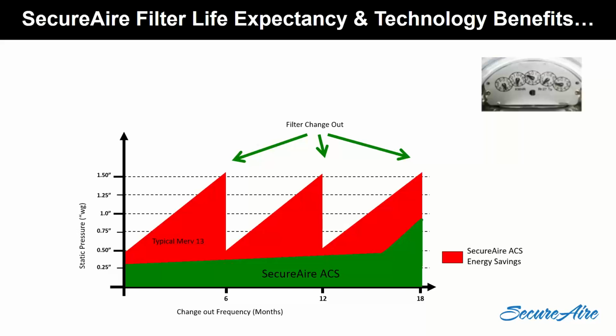So if you want to put in a Merv 13 in a 1-inch filter, that's going to be a problem. It's going to have a really high pressure drop. It's probably going to cause your system to trip on high limit due to lack of airflow. So if you want to get high Merv rating, meaning more than Merv 10, you better start getting a deeper filter, a 3 or 4-inch filter on there to get that depth.